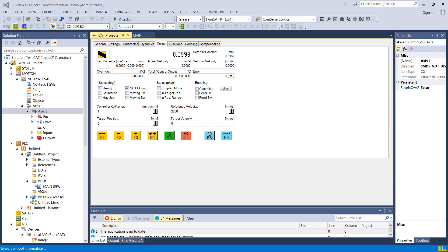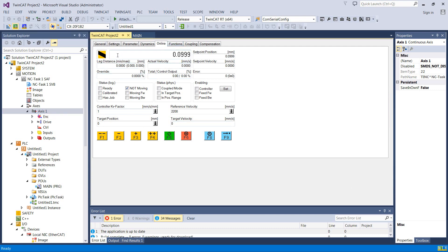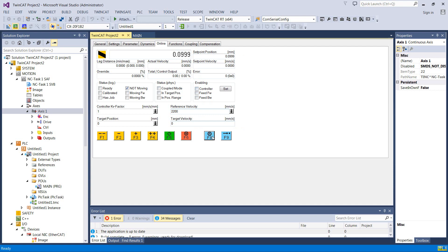So here on the online tab of Axis 1, I can look at quite a bit of information here, but this is my position, essentially. This is my set position, my actual position. So one of the things you've got to do, we have to reset it, and that just clears any faults it has from losing its high-voltage power or anything like that. So I didn't mention it, but these will have a 24-volt system and a high-voltage system. And one of the common safety categories, you'll just pull the high-voltage off of it just completely with a big contactor. So it keeps 24 volts, so it keeps all its communication going.